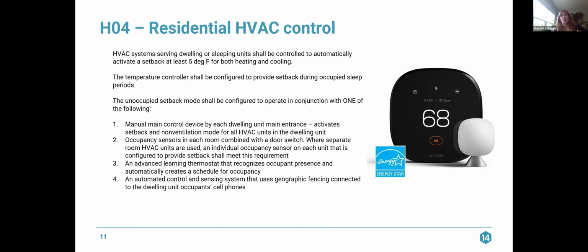H04 is residential HVAC control, and this one's interesting. So in this credit, and again, this is only available for dwelling or sleeping units. Other occupancy types cannot use this credit category. So HVAC systems serving dwelling or sleeping units shall be controlled to automatically activate a setback of at least 5 degrees for both heating and cooling. The controller has to be configured to provide setback during times when the residential unit is unoccupied, but then also during occupied sleep periods.